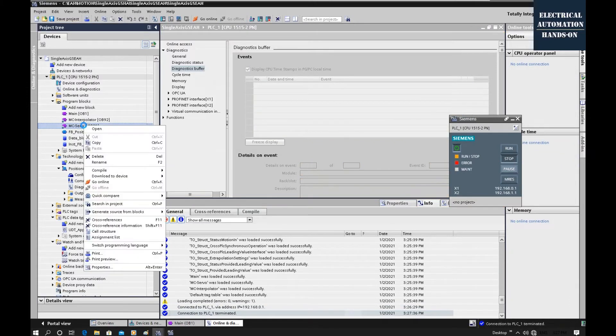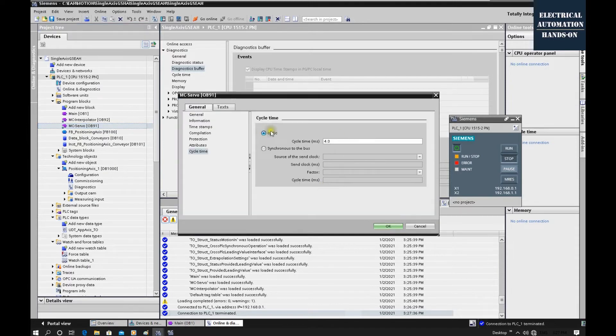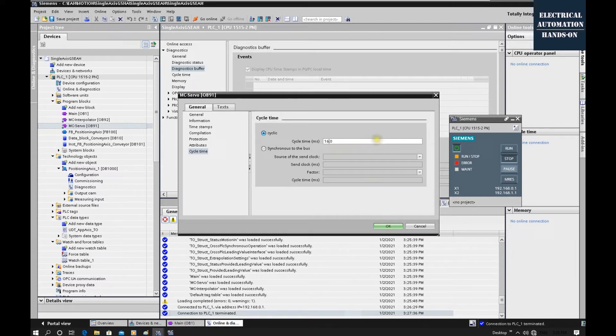To solve this problem, go offline, then right-click and click Properties. This is the cyclic cycle time — it controls the motion control cycle time. The cycle time is too short, which is very challenging for the software. For testing purposes we can increase this cycle time, for example to 16 milliseconds or even longer.